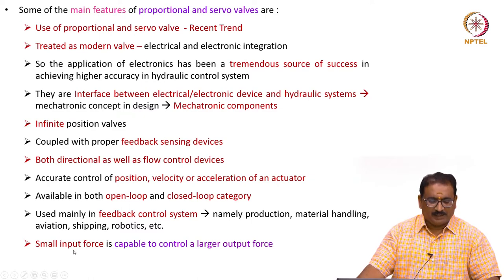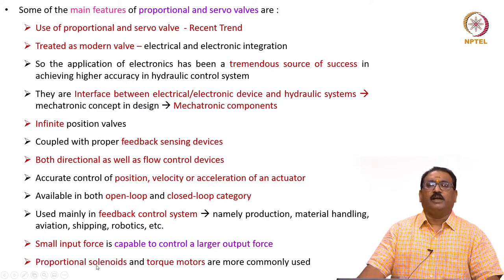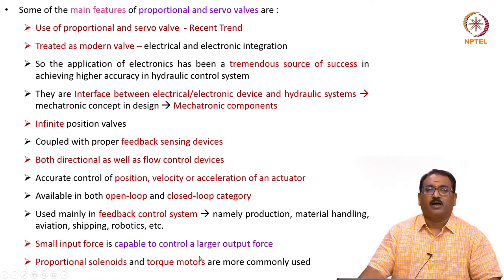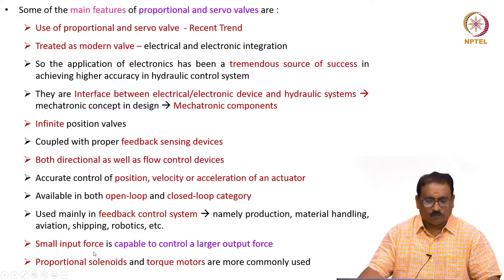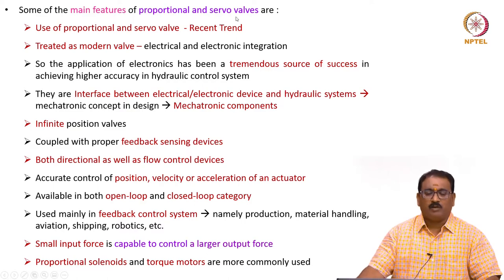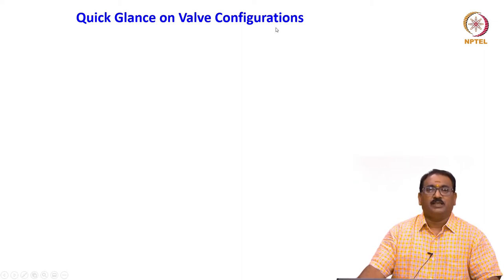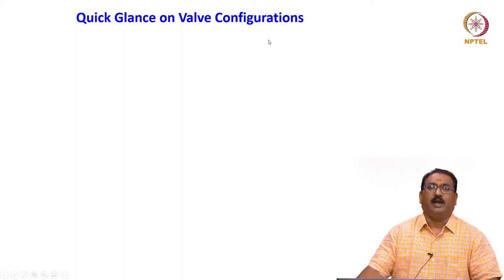An important advantage is that a small input force is capable of controlling a large output force. Proportional solenoids and torque motors are more commonly used. Please remember: proportional valves work on proportional solenoids, while servo valves are driven through torque motors. After knowing these important features, we will move on to a quick glance at valve configuration, which is essential to understanding valve dynamics in both proportional and servo valves.